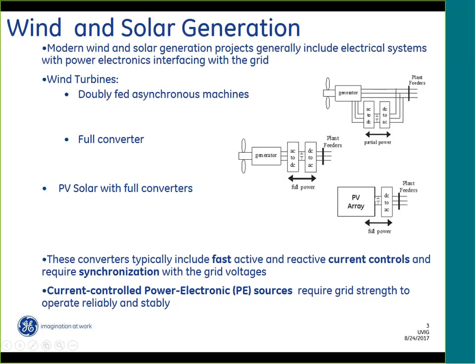We may want to differentiate the doubly fed machine, which only has partial conversion. However, from the point of view of what we're discussing, these three types of generation have similar characteristics. In general, all these generators have fast active and reactive current controls. These converters are called voltage source converters in the industry because they have a DC voltage, but on the AC side they typically have current controls. This is an important characteristic for the type of issues we're going to discuss today.